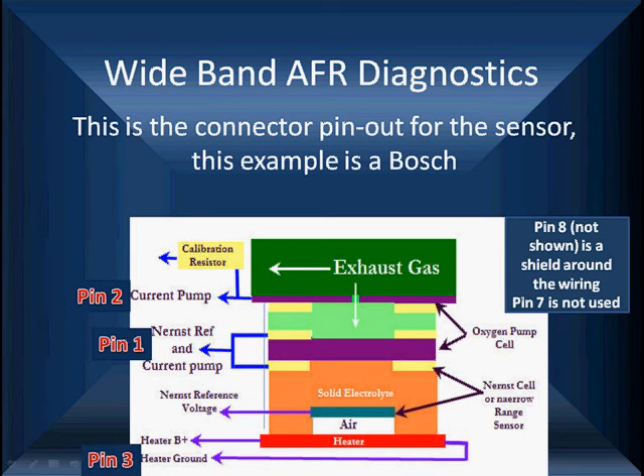And 3 is heater ground. Very critical because the heater must be working properly. 4 up at the top is our calibration resistor. And 5 is our reference voltage. This is the voltage we're trying to hold at 0.45 volts. We're going to be running current in and out of pin 2 to keep pin 5 at 0.45 volts.